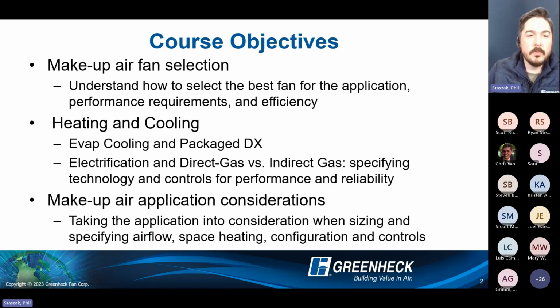We'll talk about general heating and cooling with makeup air, which is much different. We'll talk briefly on cooling, but heating is really the primary focus. Cooling is more on the DOAS side, a dedicated outdoor air system, where it's more about people versus a process. Here we're talking about process exhaust, and therefore making up for that process exhaust. So cooling is more of a luxury item, really designed more for the kitchen market than anything else.